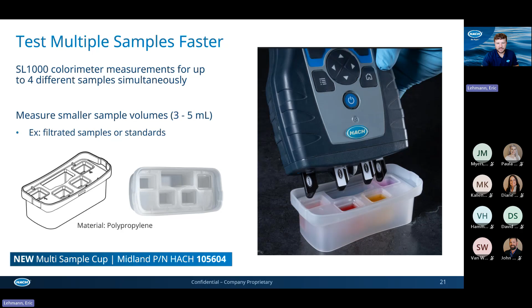So I showed you when I ran the test, I had just my one little sample cup. We do manufacture a multi-parameter or multi-sample cup, where we have independent little wells in the sample cup. So maybe I want to test for total chlorine and free chlorine in one sample or 2 different samples. Maybe I had some other samples that I wanted to run phosphorus or nitrate in. I can do that using this type of sample cup. But by default, it comes with just that one single sample cup.